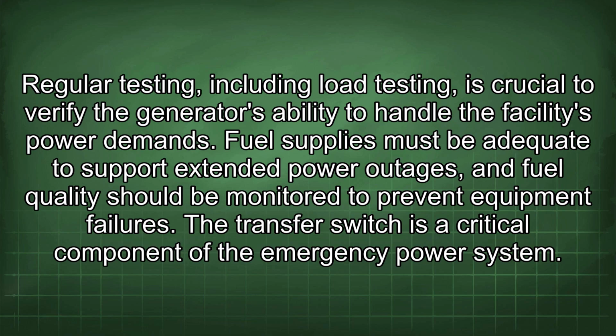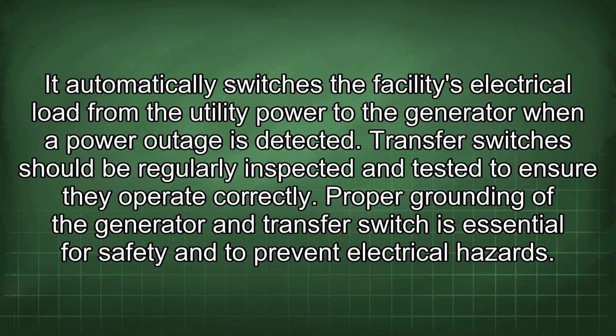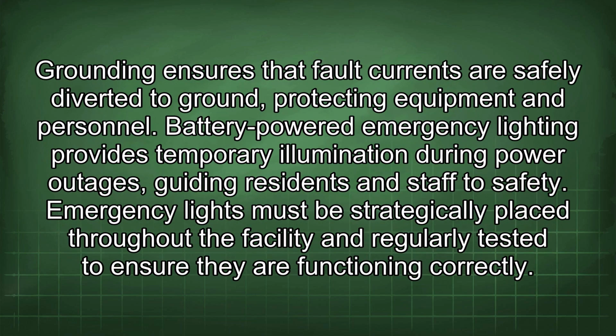The transfer switch is a critical component of the emergency power system. It automatically switches the facility's electrical load from the utility power to the generator when a power outage is detected. Transfer switches should be regularly inspected and tested to ensure they operate correctly. Proper grounding of the generator and transfer switch is essential for safety and to prevent electrical hazards.